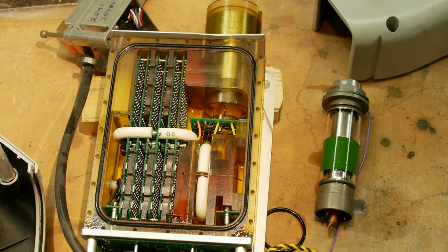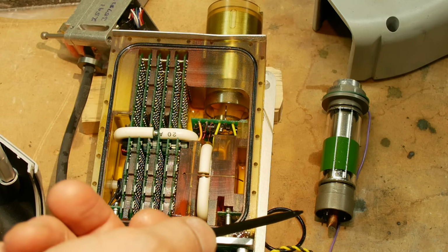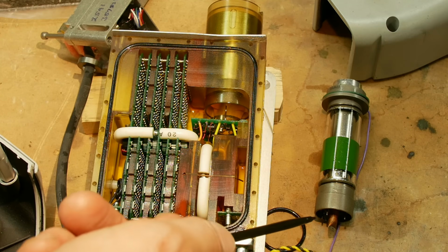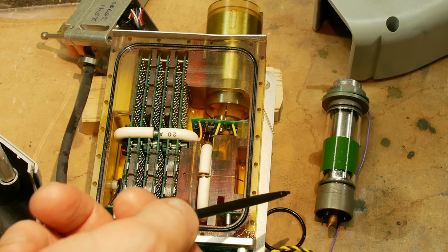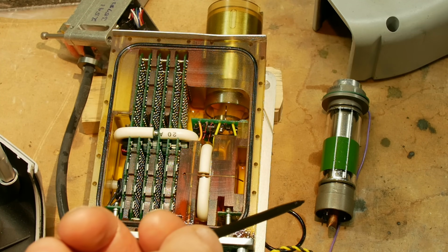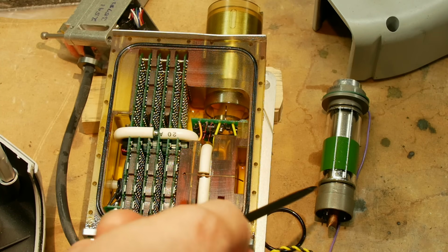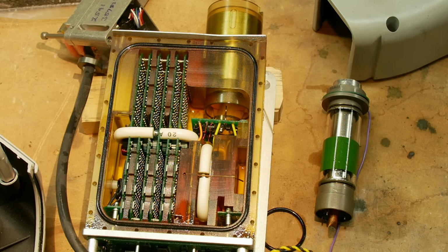And typically you would have like an op-amp or a servo control loop, monitoring this. The reason that you'd want the anode to be at 40 kilovolts and the bottom to be at 0 volts is so that you can attach your filament control circuit near ground. I mean, this is going to be 6 volts to control the filament, and it would be convenient to have all this stuff be at ground potential.